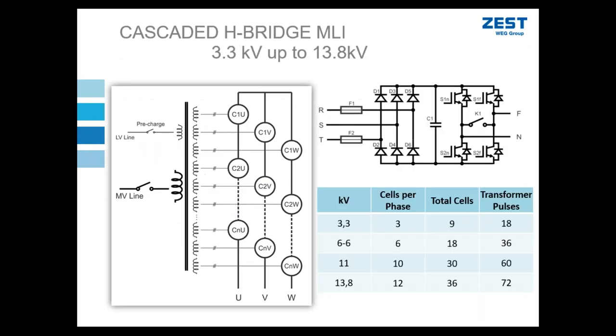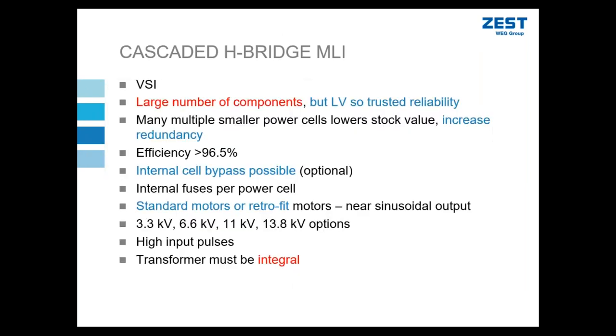The other thing, because I'm building up each phase voltage with a number of smaller voltages, I have this kind of redundancy where I can almost afford to lose, especially in the case of 6.6 kV and higher, because I've got six or more cells per phase. I'm almost in a position where if one power cell becomes faulty and I'm able somehow to bypass it, I can utilize this VSD at slightly reduced capability, but it is possible to still operate for some time. So we have this increased redundancy. This also helps to reduce the spares cost compared to the NPC topology.